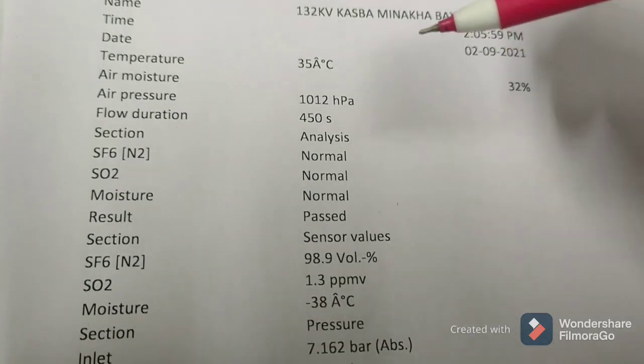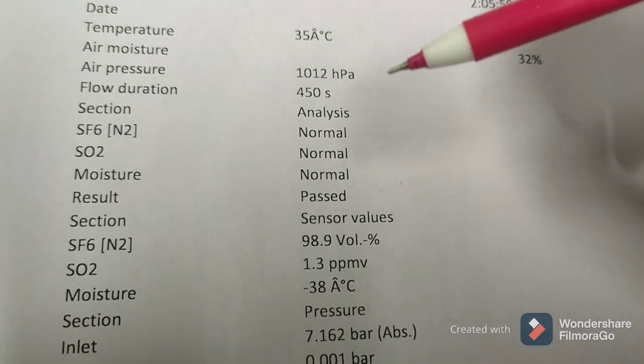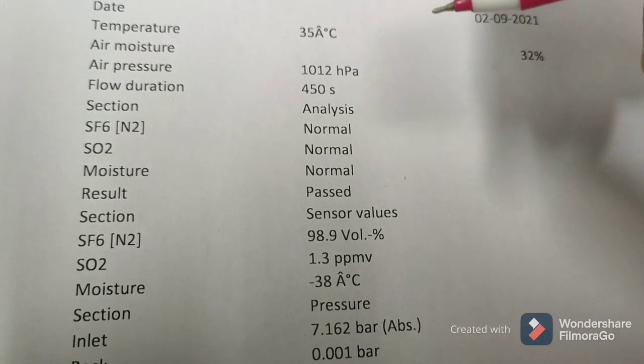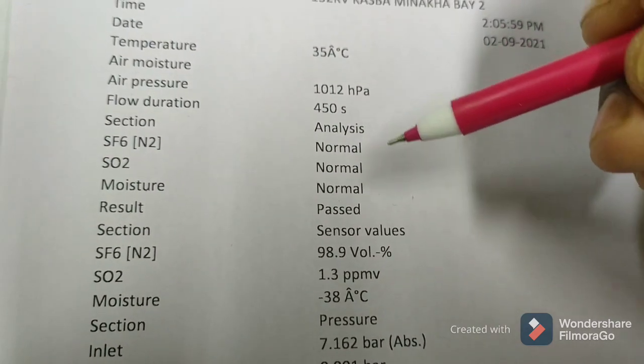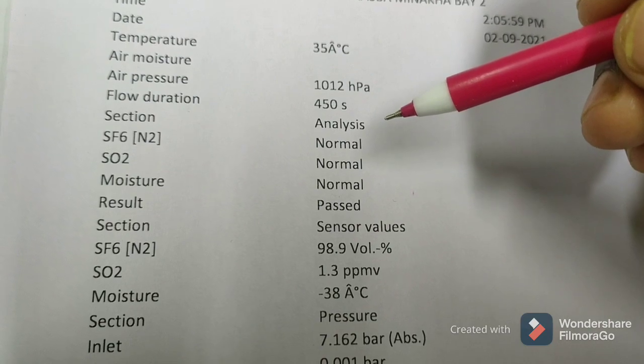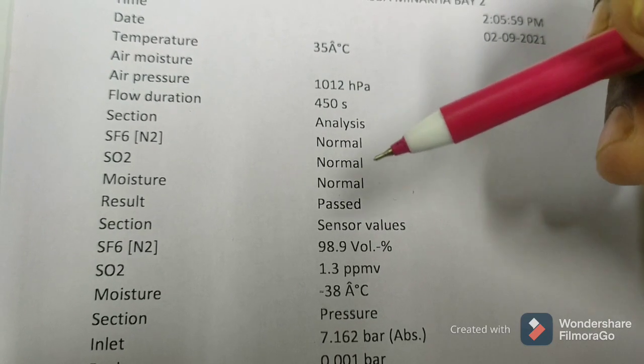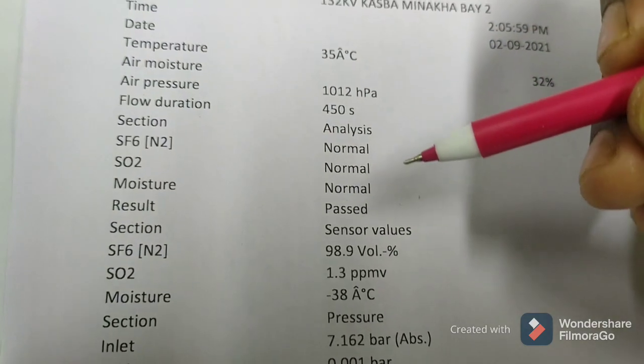By this analysis, we have confirmed that the gas inside the interrupter is in good condition and can be used for operation.